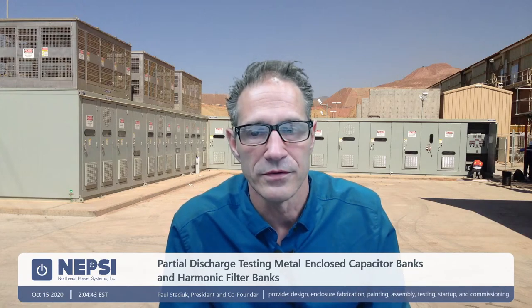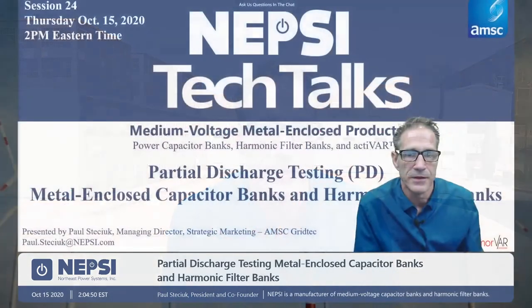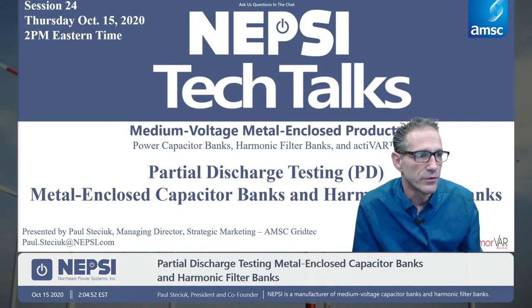but when we are talking about how long the equipment will last, really, partial discharge testing is the key test for that. And again, those other tests do not always reveal the defects that can be revealed by the partial discharge test. So we're going to get on with the presentation, and you can see here partial discharge testing.